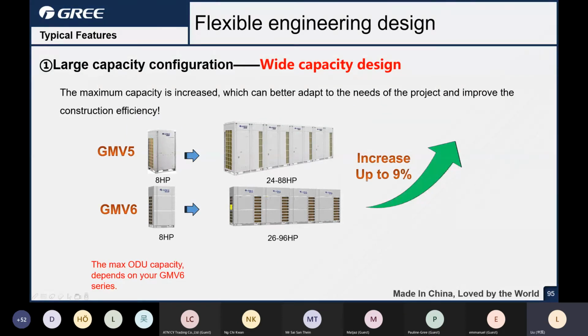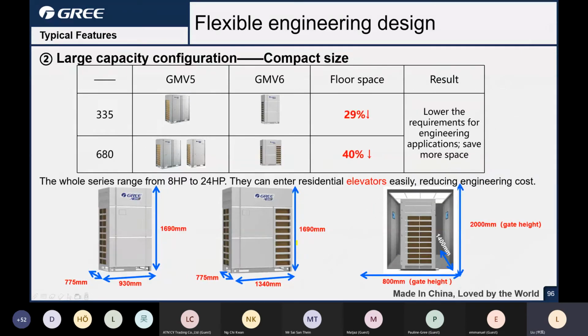The first one is the capacity. It's an increase of about 9%. The maximum can be up to 96 horsepower. That's the maximum combination. Okay, and also the size. The GMV6 is more compact for the floor space. For the single compressor units and double compressor units, both of them, the dimension is smaller. So that means the space requirement for installation is also smaller. And a lot of good news is for the transportation. You can put this into the elevator directly, and that's good for your transportation and the installation.